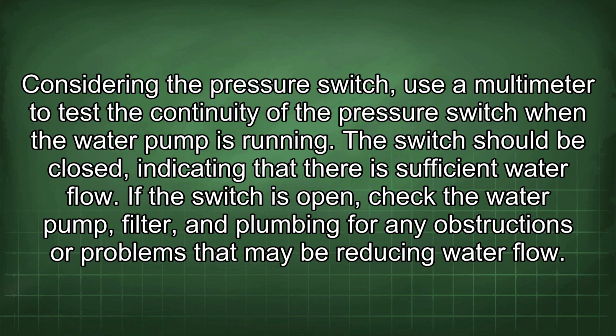Considering the pressure switch, use a multimeter to test the continuity of the pressure switch when the water pump is running. The switch should be closed, indicating that there is sufficient water flow. If the switch is open, check the water pump, filter, and plumbing for any obstructions or problems that may be reducing water flow.